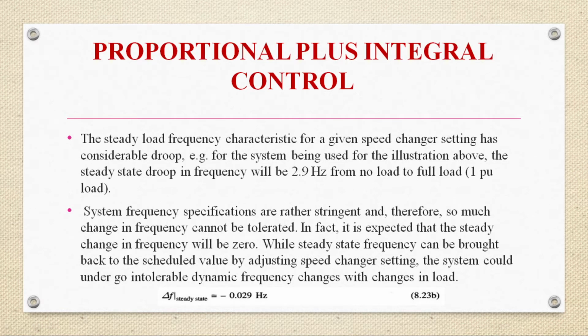While the steady state frequency can be brought back to the scheduled value by adjusting the speed changer settings, the system can undergo intolerable dynamic frequency changes with changes in load. So we can bring the steady state frequency to its setting by changing the speed changer setting, but we cannot adjust the dynamic frequency changes whenever there are changes in the load.